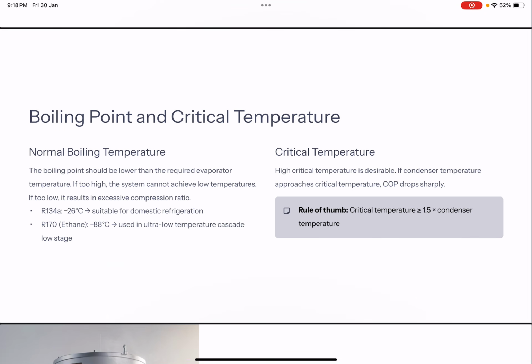The key consideration for why the boiling point has to be lower than the required evaporator temperature is that we want a positive pressure in the evaporator. If the normal boiling point is not lower, then we need to operate that system under vacuum, and operating the refrigeration system under vacuum is a costly affair because maintaining vacuum in the evaporator would be a challenging aspect. So, along with making sure that the required low temperatures are met, it also ensures that the evaporator is always operating under positive pressures. So the key property is that the normal boiling point should be much lower than the required evaporator temperature so that the evaporator pressure is always positive.